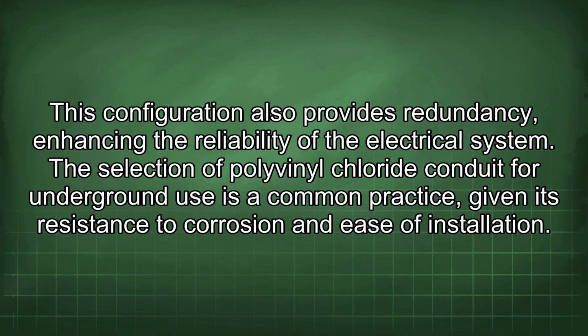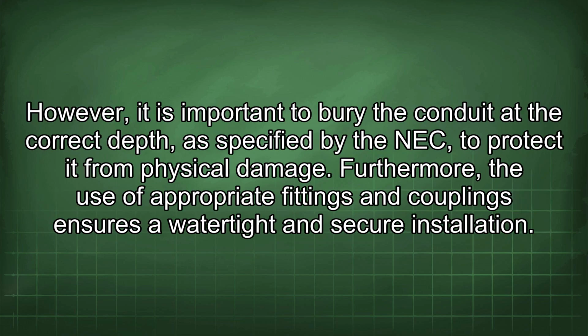The selection of polyvinyl chloride conduit for underground use is a common practice given its resistance to corrosion and ease of installation. However, it is important to bury the conduit at the correct depth, as specified by the NEC, to protect it from physical damage. Furthermore, the use of appropriate fittings and couplings ensures a watertight and secure installation.